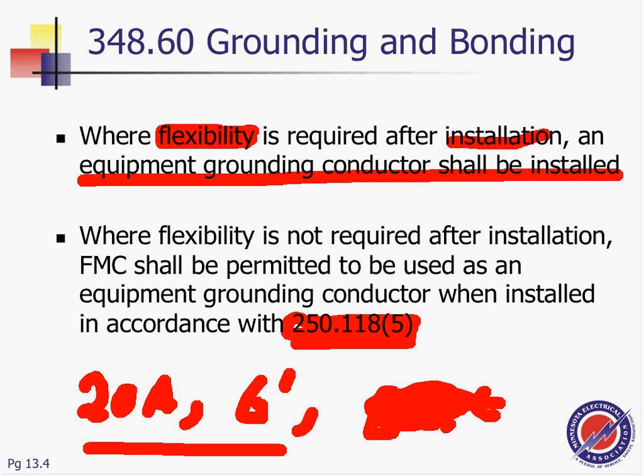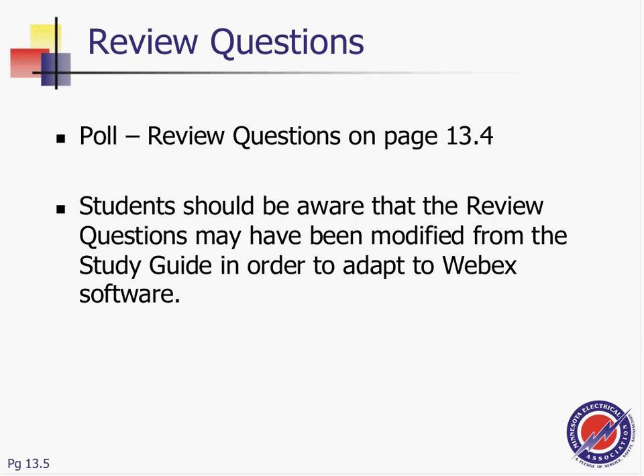So you have to pull an equipment grounding conductor if it's used for more than 6 feet, or if it's used for flexibility. Okay, any questions about grounding? I can't emphasize the importance of grounding enough.